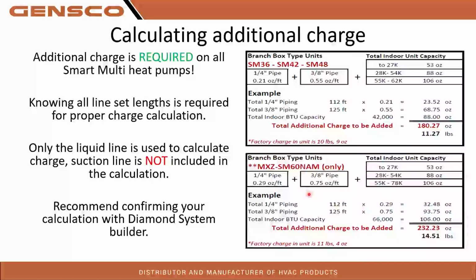What you do is, once you measure out all your line sets, figure out how long everything is and separate 1/4 from 3/8, you'll take all the 1/4-inch liquid line you have, times it by 0.29 in this situation, and that's how much charge you will need to add for your 1/4-inch pipe. Next, you take all the 3/8 liquid line you have, times it by 0.75, and that's how much charge you need for your 3/8 liquid line set.